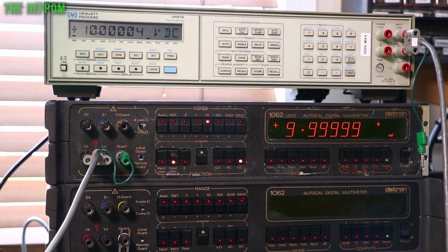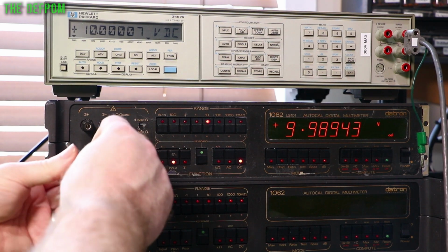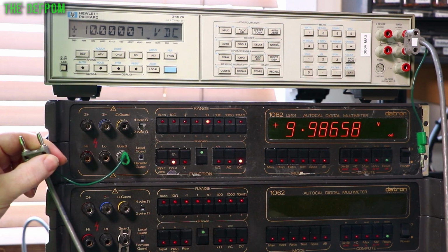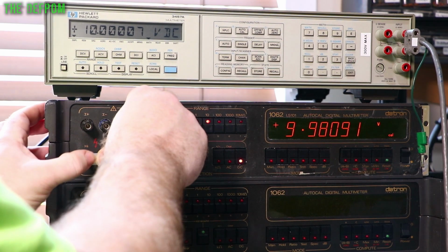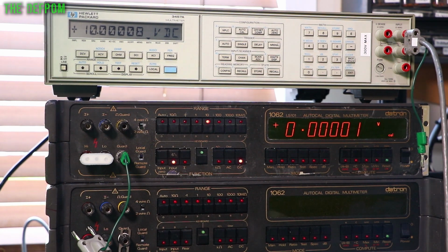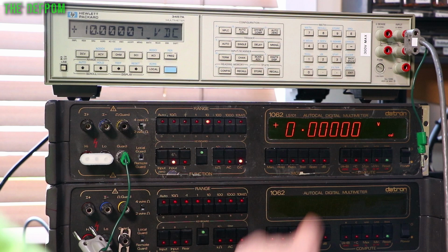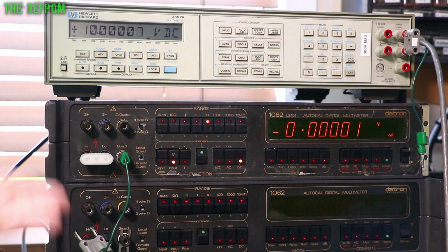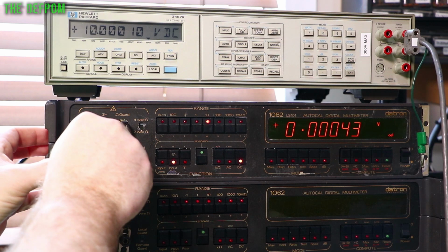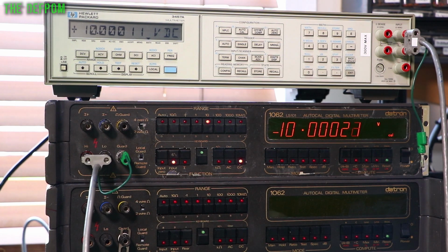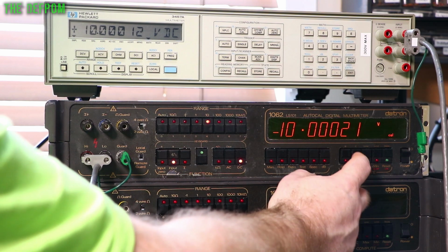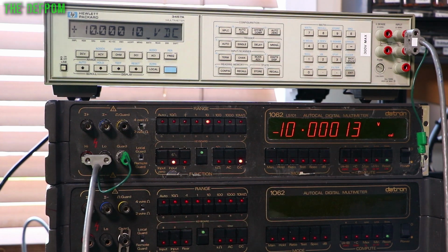Okay, and now what I've got to do is actually reverse the polarity on this connector. So I need to get this, and I think I actually have to do another zero first. Yes, I do. So we did a gain on that one, then we do a zero. Just to make sure it's definitely okay, I'm just going to verify it looks okay. Looks good. Do another zero. This is what the manual says, even though it says it's fine. Alright. Then we do the negative 10 volts, which is reverse polarity. Okay, and then we hit gain again on this one, and that sets minus 10 volts.